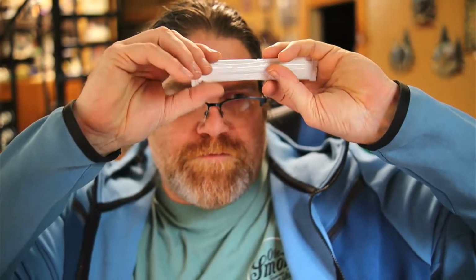So if you look here, you can see there's no UPC or UDI on it. If I flip it over, none there. But on this side they put the IVD symbol. It's hard to do both at the same time. So they do have the IVD symbol. They also have the temperature storage symbol, and then they have a CE marking, so this is a CE mark product. And then they have the single use only symbol, and some lot information. So this isn't even meeting all the European requirements either. It's meeting some of them, but not all of them.